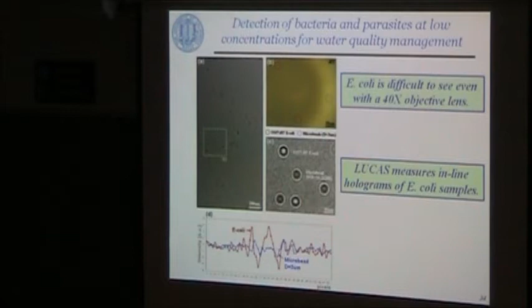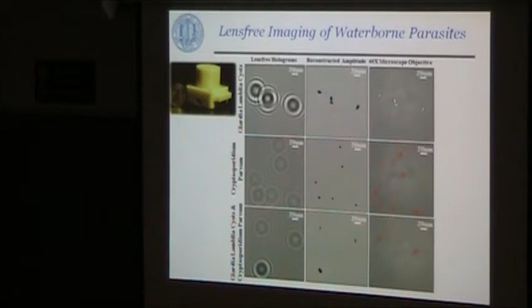These are some other waterborne parasites that we've imaged. These are Giardia and Crypto samples. The holograms are captured with a field portable microscope like this, then reconstructed, and this is a comparison. Again, the same contrast enhancement is also visible here compared to a 40x, as shown here. In this case, again, this field of view here is 24 millimeters square, and we're looking at a depth of field of around 1 millimeter. So you have there a 24 millimeter cube volume screened, which is fairly large because a conventional 40x will be looking at, roughly speaking, 0.5 or less millimeters square. That's why you need to kind of scan or use some enrichment technique.